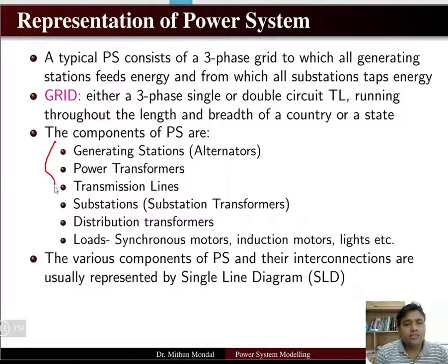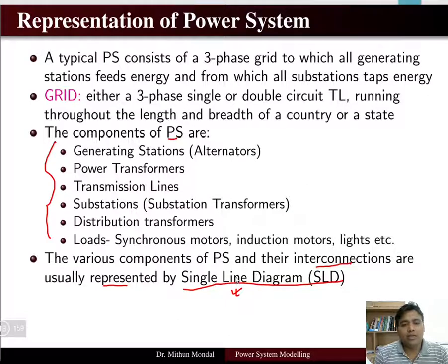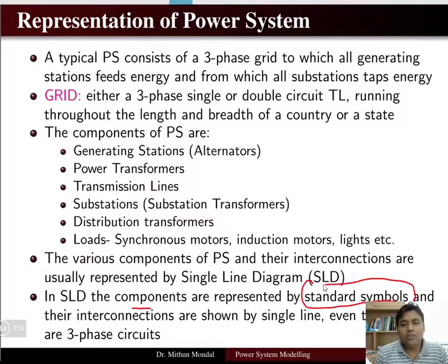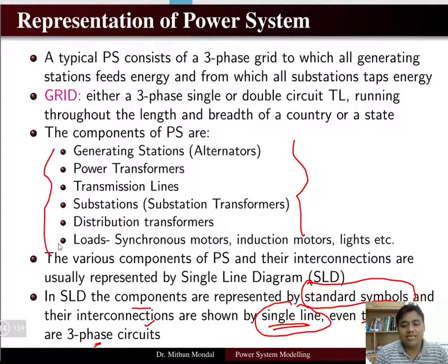All these components and their interconnections are usually represented by a single line diagram, also known as a one line diagram. In a single line diagram, the components are represented by standard symbols and their interconnections are shown by a single line, even though they are three-phase circuits. Whether you are dealing with a three-phase circuit or single-phase circuit, there will be only one single line.